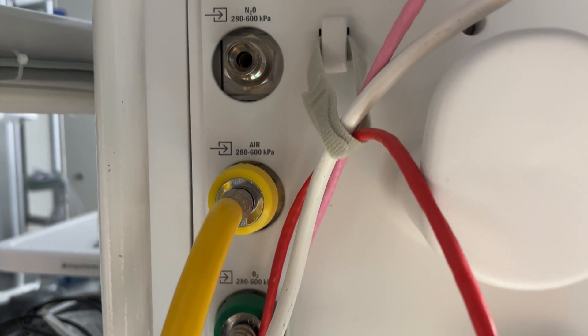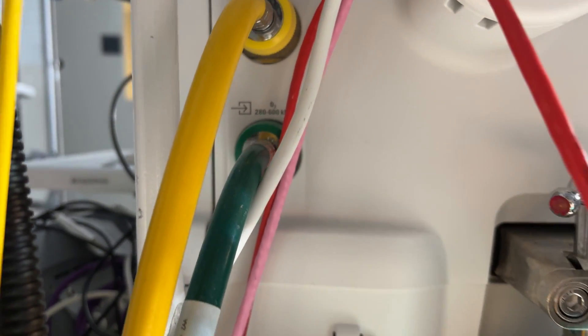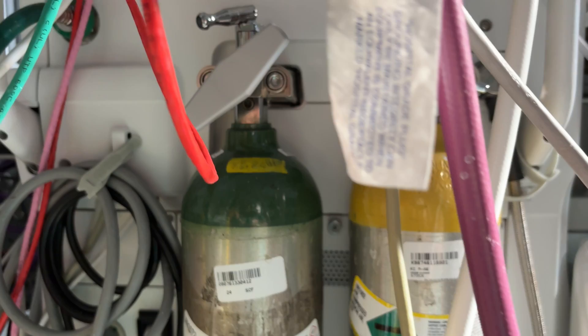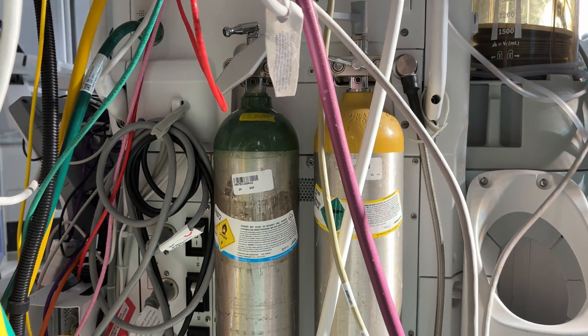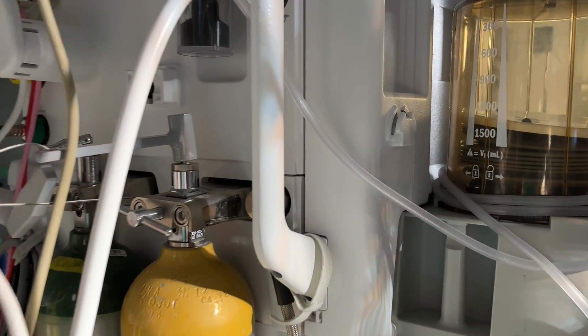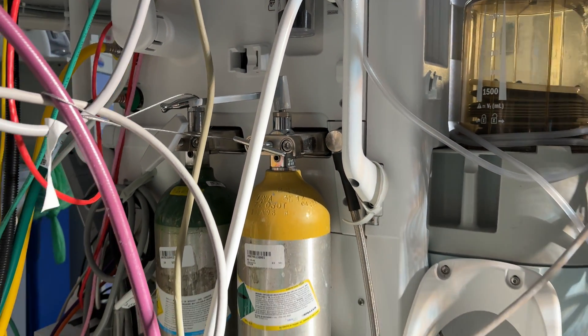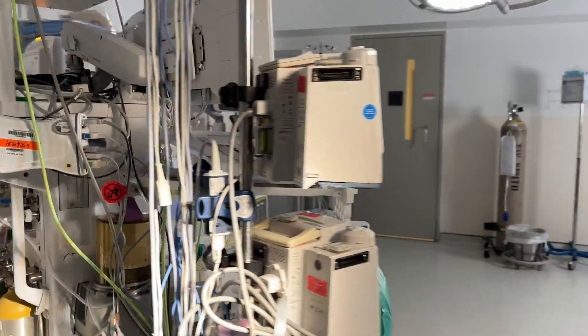This is an important safety feature. Another critical safety feature is the presence of these backup e-cylinders with oxygen and medical air, which are also not interchangeable with each other. It's worth pointing out that these e-cylinders are filled at typically a much higher pressure, with oxygen around 2200 psi when full. Inside the machine, a pressure regulator brings this down to about 45 psi. These tanks are opened and closed manually, and it's important to ensure that they're closed when not in use, because otherwise they can leak slowly and become empty over a period of days.